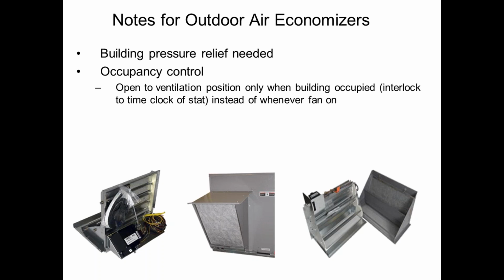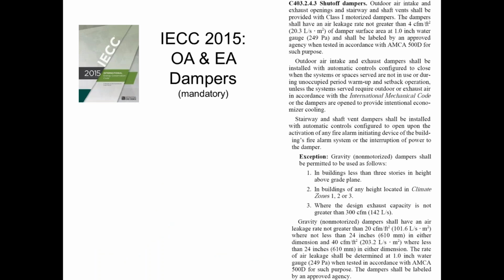So one of the easiest ways to do that is to buy a thermostat that has an extra output on it for occupancy, because the thermostat is probably the only thing in the building that knows the occupancy schedule, assuming someone programmed it. So whenever the stat goes unoccupied, it sends a signal up to the damper for the damper to shut for ventilation reasons. The damper could still modulate open for free cooling economizer reasons, but it won't open for ventilation reasons. So you need to have that interlock for all outside air dampers, including economizers.